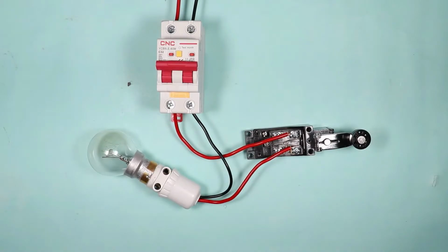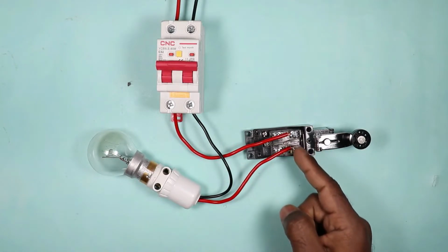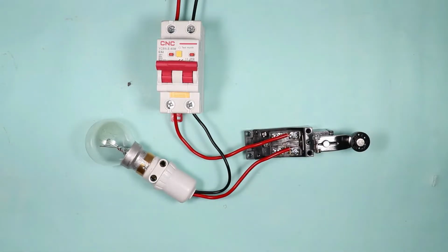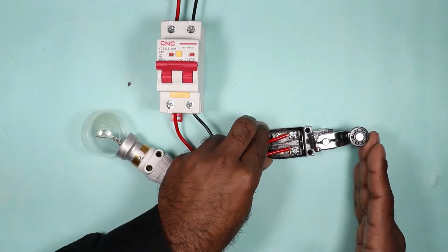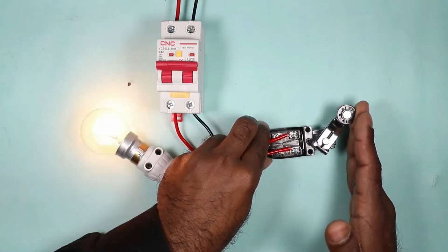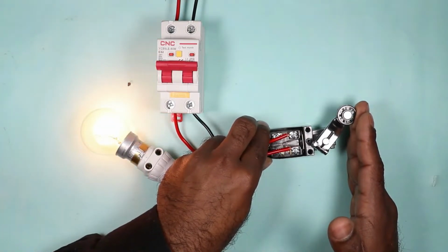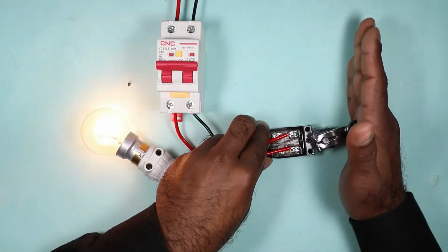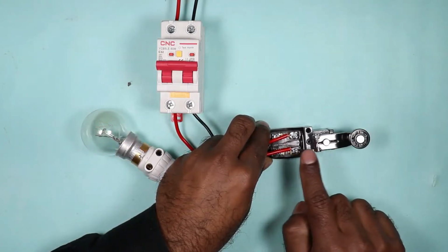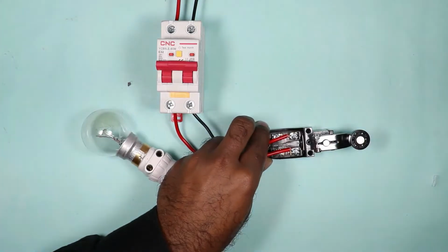On turning on the MCB, you can see the lamp is not glowing. This lamp is in off condition because the connection is in NO contact. Let's assume this switch is mounted with a conveyor belt. This means the object which is coming will touch this switch. When it touches the switch, then the contact will change in the switch and the lamp will start glowing. This means now the limit switch is generating an output command. When the belt releases the switch, then the limit switch comes back to its original position and our lamp will turn off.